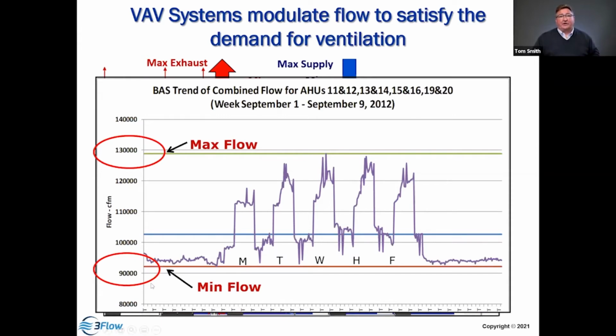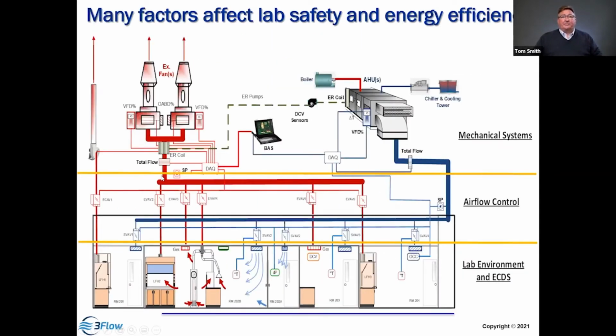The question becomes, are these the right numbers? Do we have the right amount of flow through the building? And how would we know? So we can take a look at the operation of the systems, and I like to divide it into 3 zones. The first zone, what happens below the ceiling, right? Our hoods and our exposure control devices and our laboratories, that's what most of the users and the occupants see. And then there's the airflow controls where we find above the ceiling and the interstitials in the penthouses and so forth. Those are controlling the airflow. And then we have our mechanical systems that are in the penthouse, on the roof, and in the mechanical rooms. These systems all work together to achieve this objective.